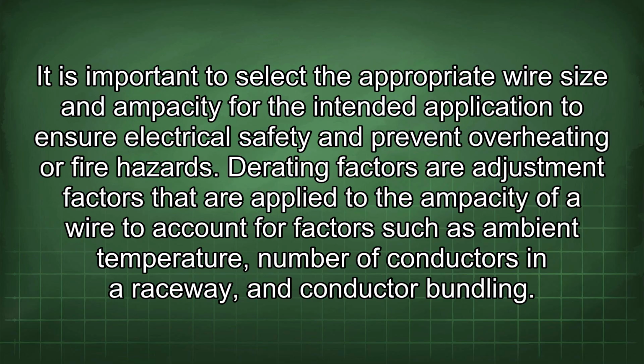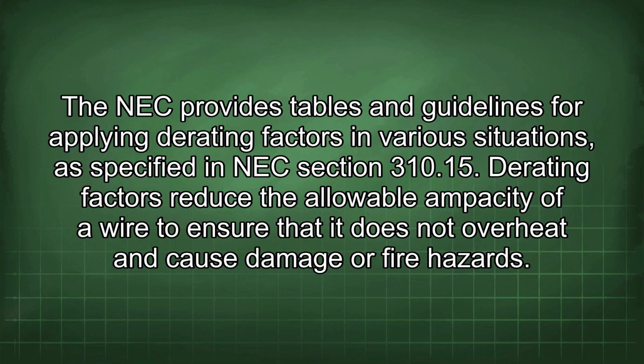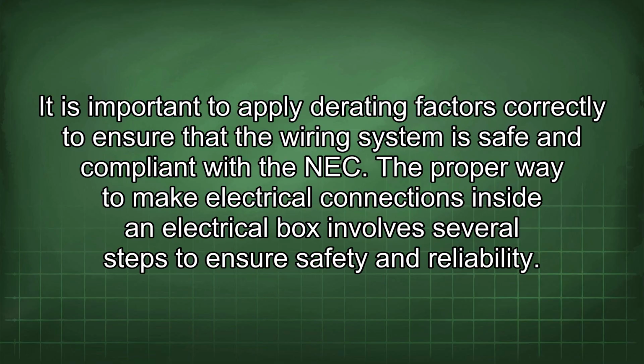Derating factors are adjustment factors that are applied to the ampacity of a wire to account for factors such as ambient temperature, number of conductors in a raceway, and conductor bundling. The NEC provides tables and guidelines for applying derating factors in various situations, as specified in NEC Section 310.15. Derating factors reduce the allowable ampacity of a wire to ensure that it does not overheat and cause damage or fire hazards. It is important to apply derating factors correctly to ensure that the wiring system is safe and compliant with the NEC.